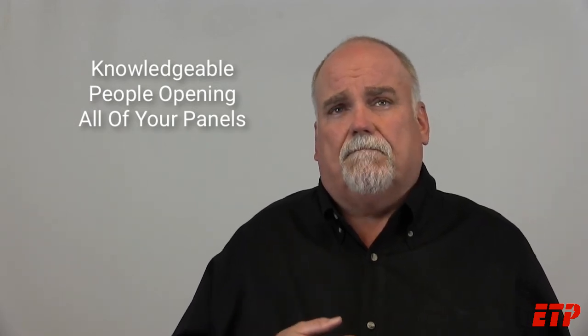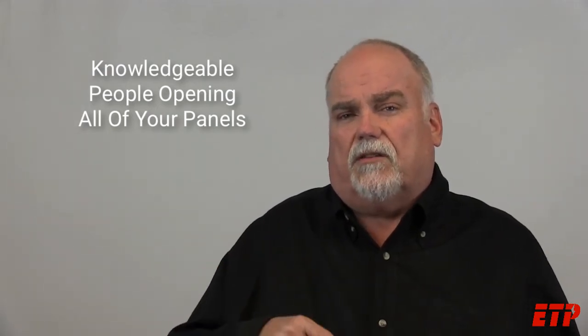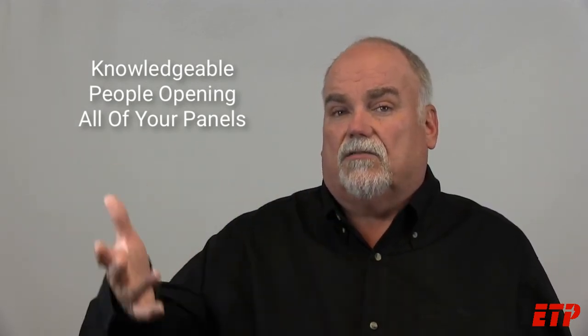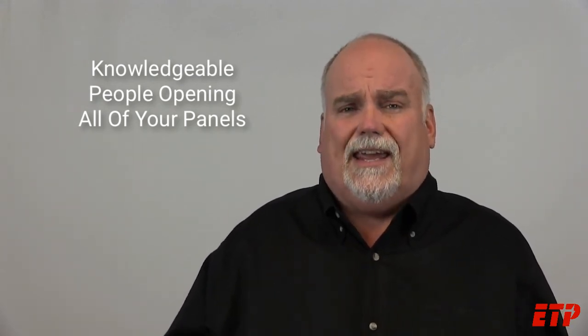These things could be a small National Electrical Code issue, like maybe a wire wasn't sized properly, or the breaker wasn't sized properly for the wire. Maybe it was close. Sometimes you need to tell the facility this so they can fix that. But sometimes it's drastic problems. I remember a tuna can being used as a junction box one time. I don't think tuna cans are allowed by the National Electrical Code, last time I checked.